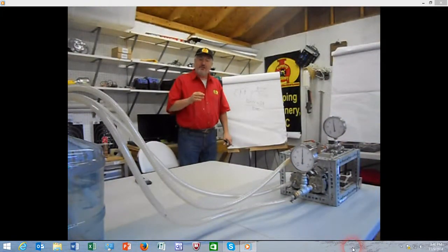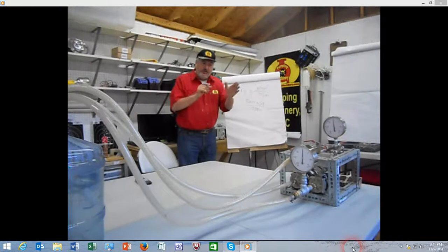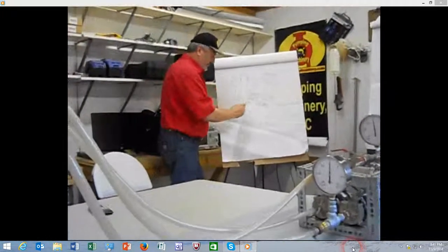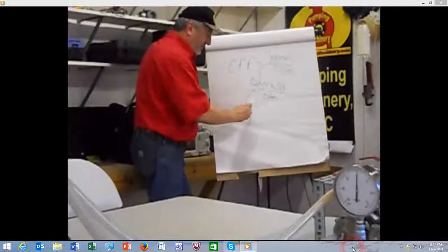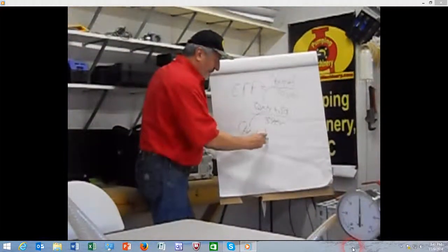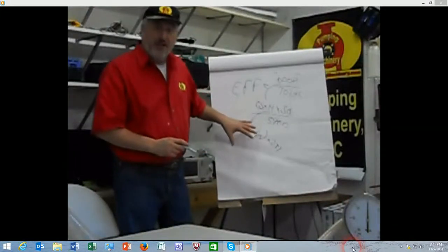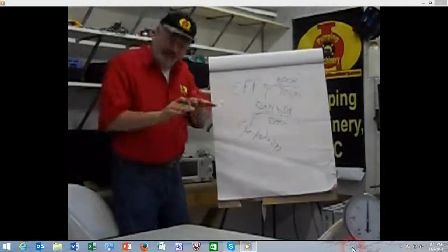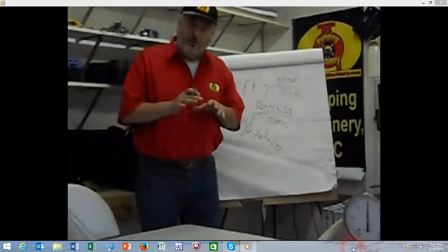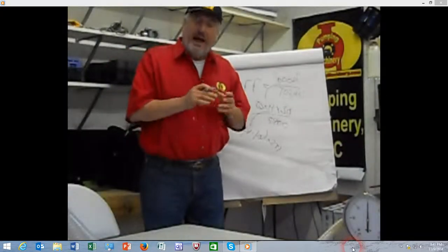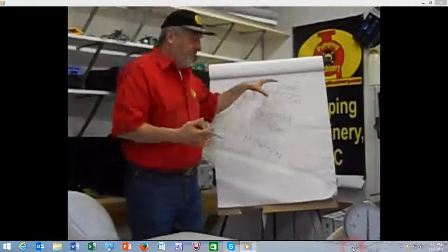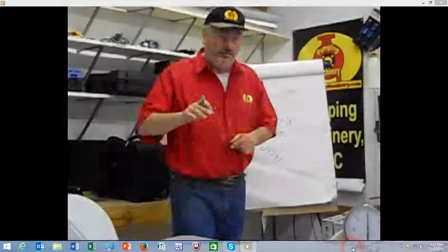In the last several modules, we discussed how the pump head is calculated, that being the difference between discharge minus suction times 2.31. Discharge minus suction times 2.31 in the US units will produce the pump head. So let's do an experiment. We will see how the efficiency flushes out through a formula and the measurement. So let's start the pump.